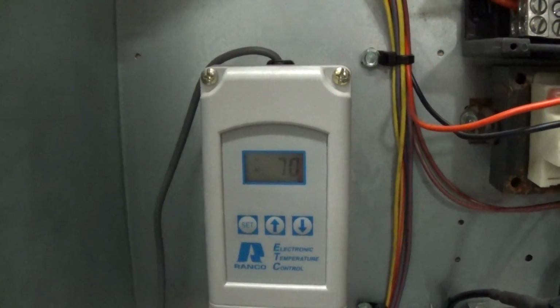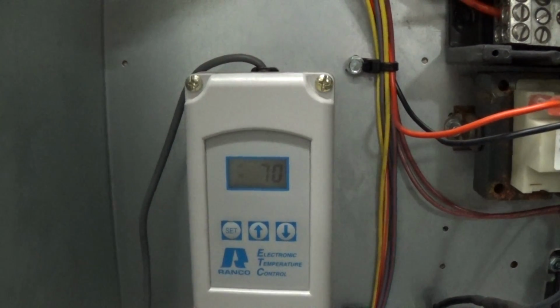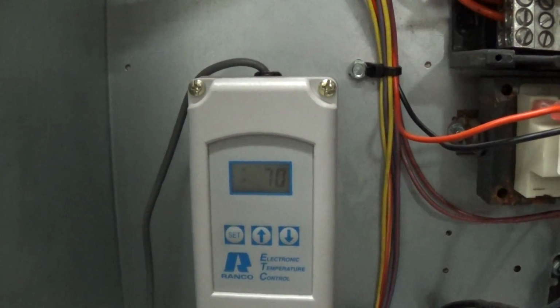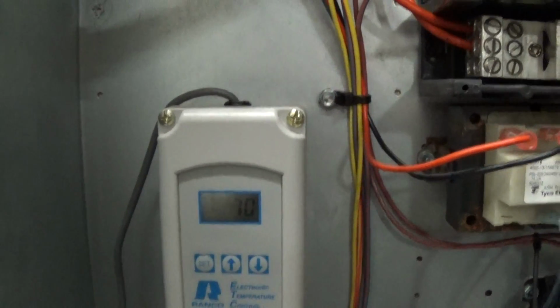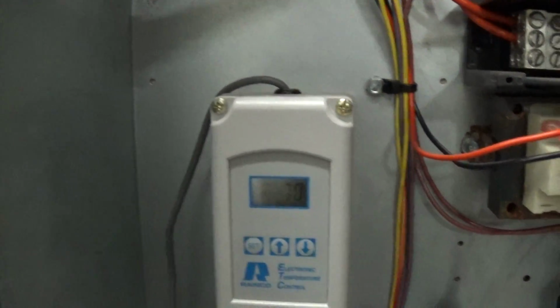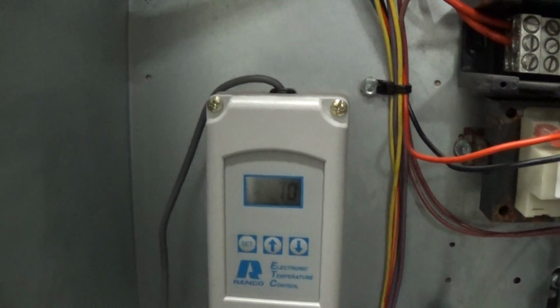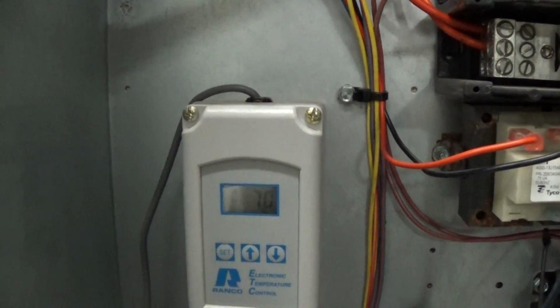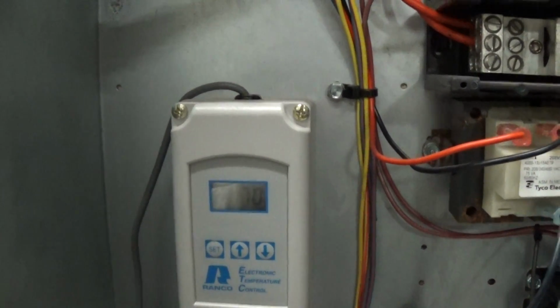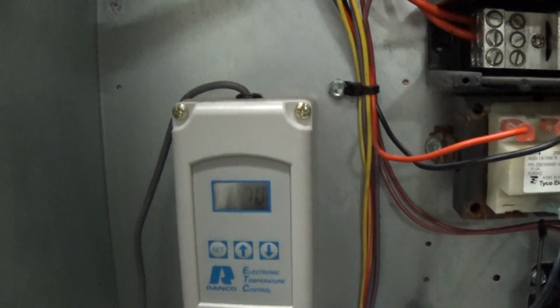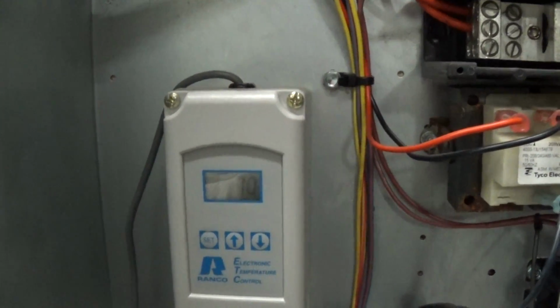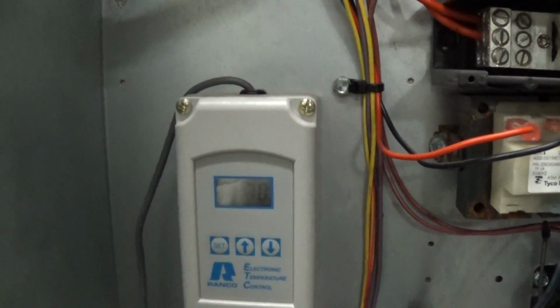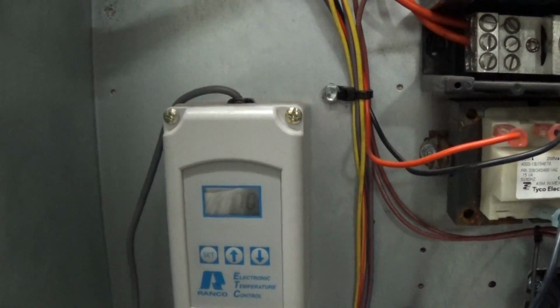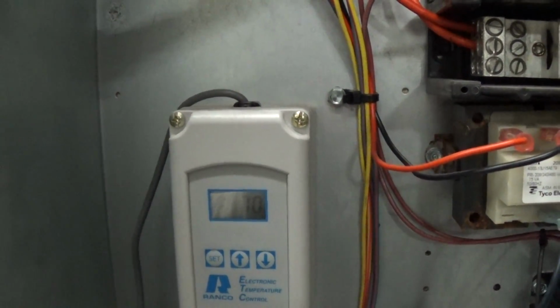Now the idea of having the set point the same for both compressors is we're going to chill down, okay? The compressor's going to turn off when we meet the set point or set points. So now our temperature will start rising a bit. When you get 2 degrees above the set point, in this case, compressor 1's going to turn on. Now if compressor 1 can't handle the load, it's going to creep up a little bit. In this case, we'll let it creep up 1 degree above, because we have a 3 degree differential, and then the second compressor will turn on also. That's the best way to do it to get good efficiency in staging.